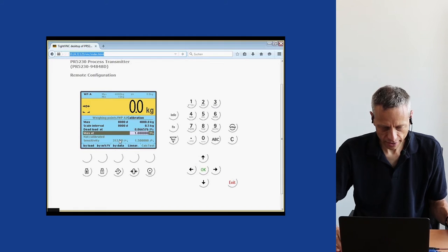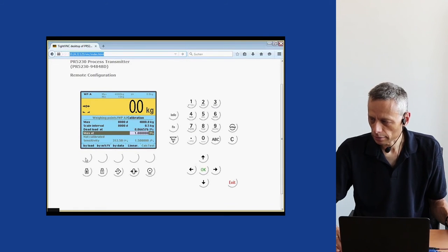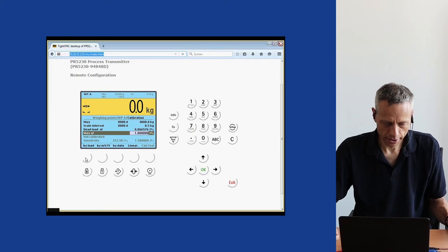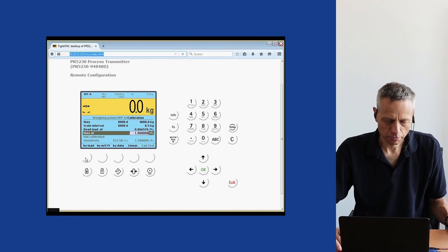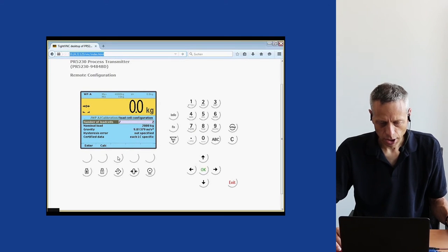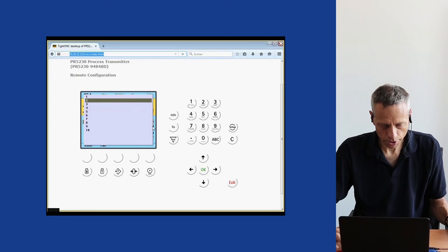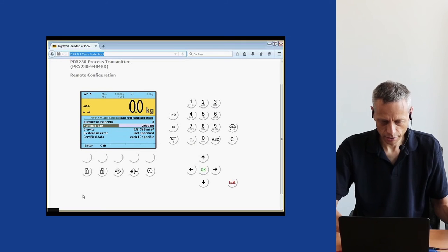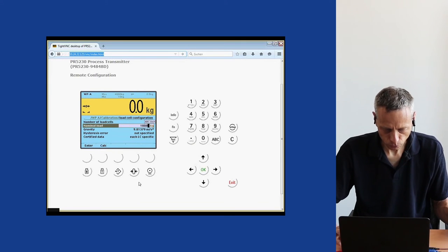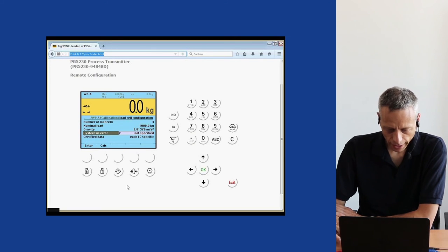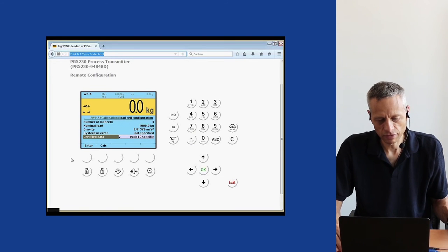The next step is setting the max value. We have the choice to calibrate the scale by load using calibration weights, but as with vessels, using calibration weights is quite time consuming and mechanically difficult. We also have the possibility to do a calibration by load cell data. We click on Data and enter the number of load cells — up to 10 can be entered, and we choose 4. We enter the capacity of each load cell, which in this case is 1000 kg. We can choose an individual gravity value, enter a specific hysteresis error listed on the load cell certificate, and enter specific values for each load cell taken from the calibration certificates.